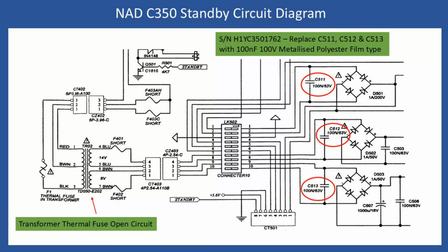this small startup transformer provides 2 output voltages. So it provides 14 volts and also an 8 volt supply. And unfortunately what happens is that any of these small 100 nanofarad capacitors will fail short circuit, which means that excess current is drawn through the standby startup transformer, and it reaches a point in terms of temperature where the thermal fuse will operate, and then you have to replace the transformer.